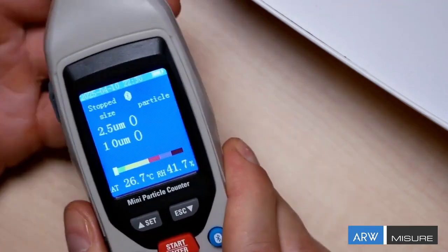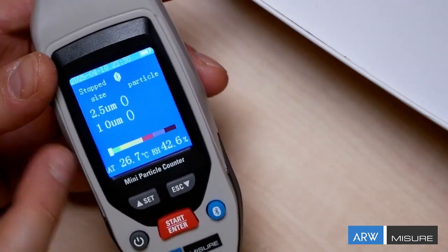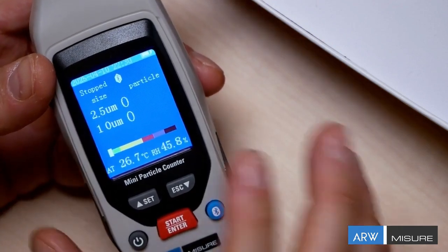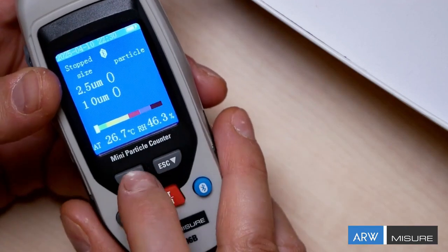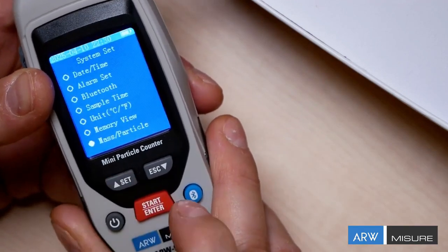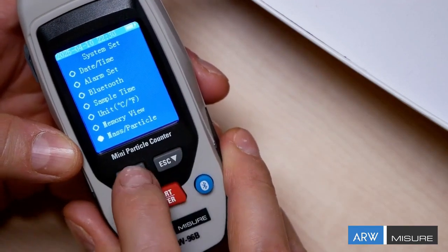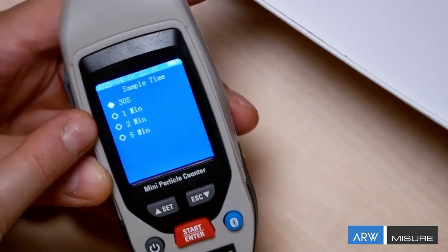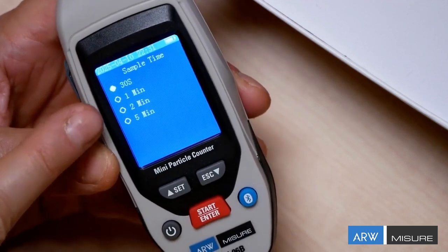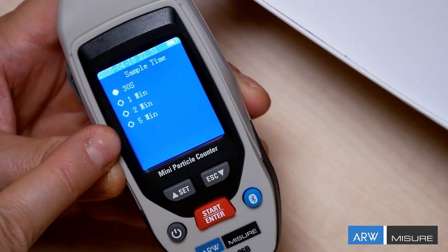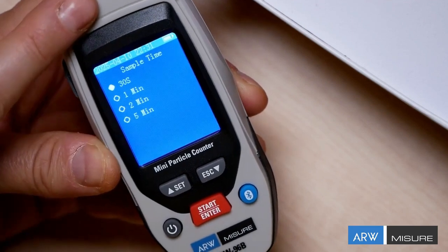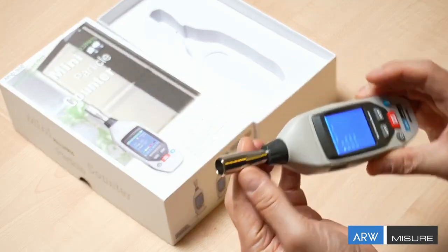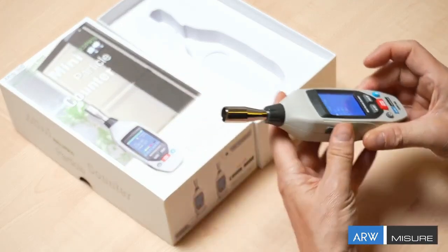All the fine dust particles that are detected through an acquisition system will be counted and displayed directly with a progressive number, depending on the setting we have chosen. This setting is always selected within the menu, which is the sampling time. This allows us to set the acquisition time from 30 seconds, 1 minute, 2 minutes, to 5 minutes, during which the suction pump we have is activated, in the, let's say, outermost part of the instrument.